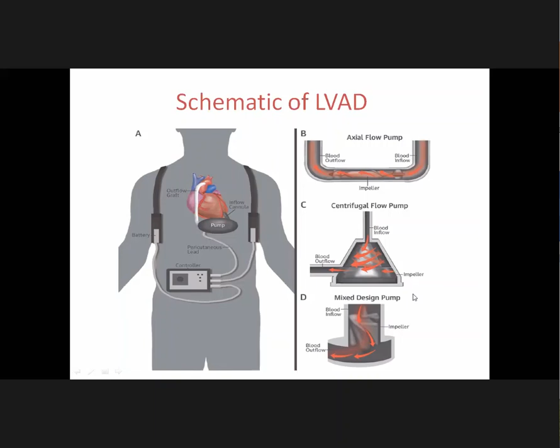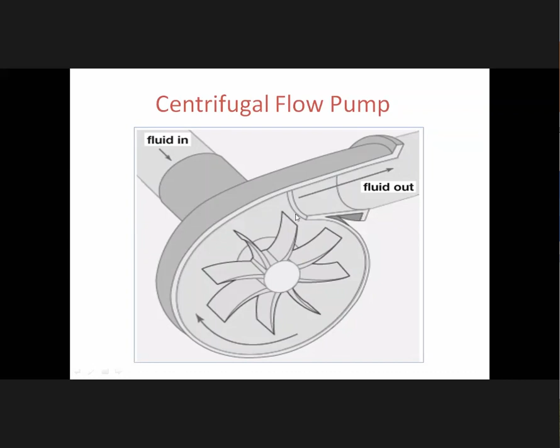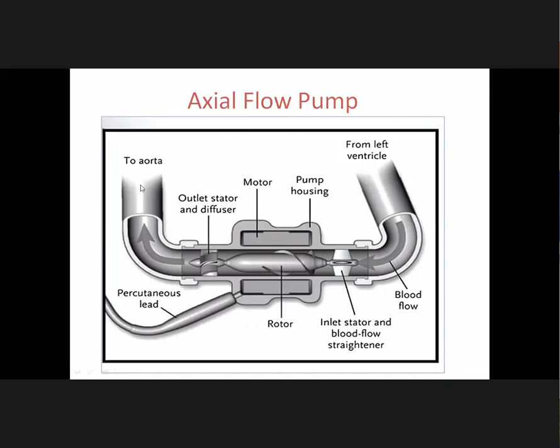This is how a centrifugal pump works, where the fluid comes into the conduit, and there is a circular blade with a turbine-like configuration which pumps the fluid out of the conduit. And this is an example of a rotor system which gives an axial flow, where we have a central rotor which is continuously rotating, which helps in driving out the blood that comes from the left ventricle. The blood flows through the inflow cannula to the rotor. From here, the rotor sends out the blood in a continuous axial fashion.